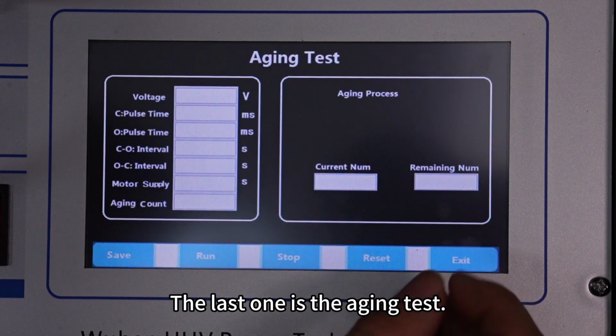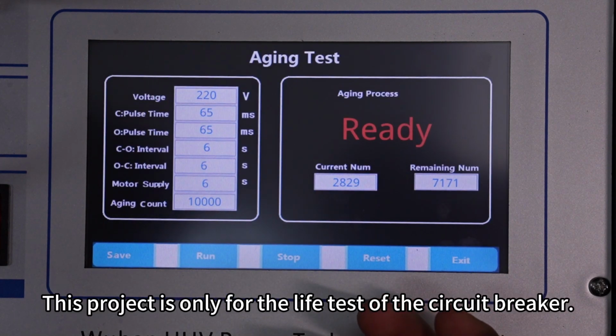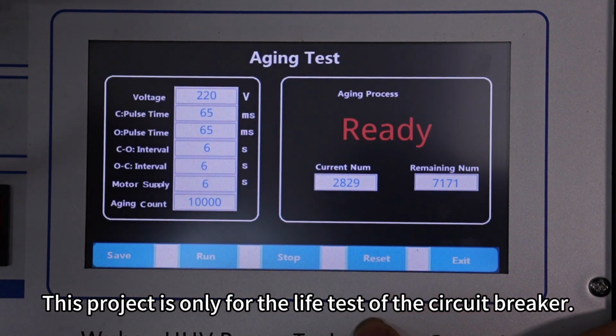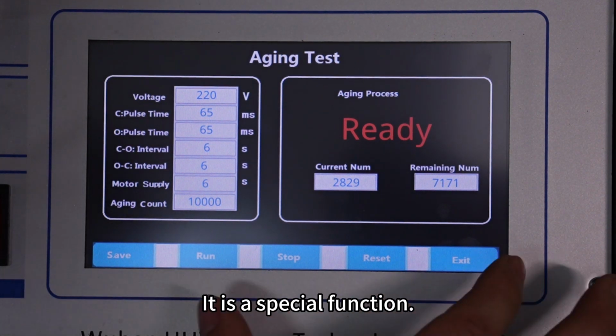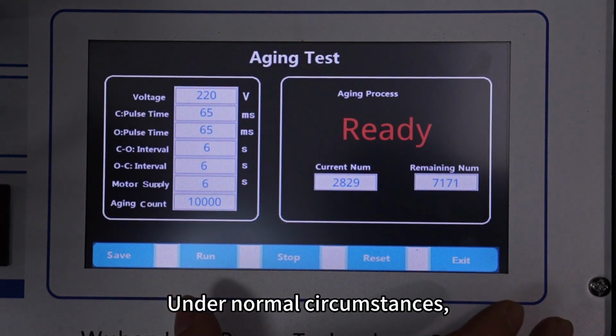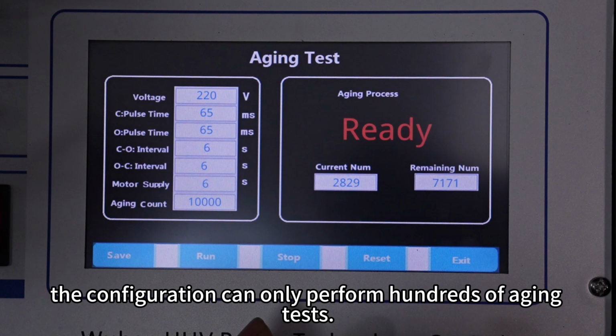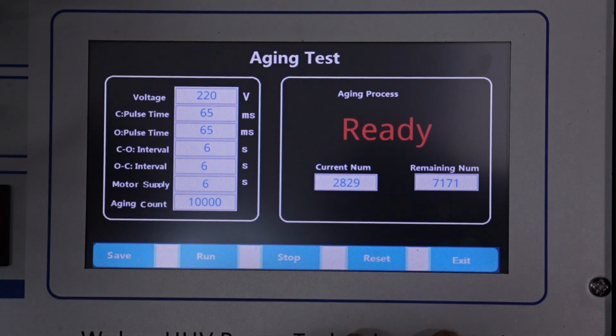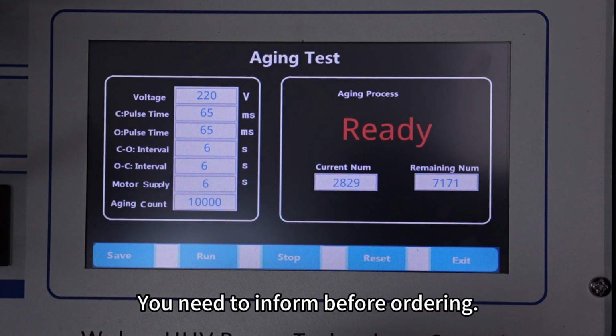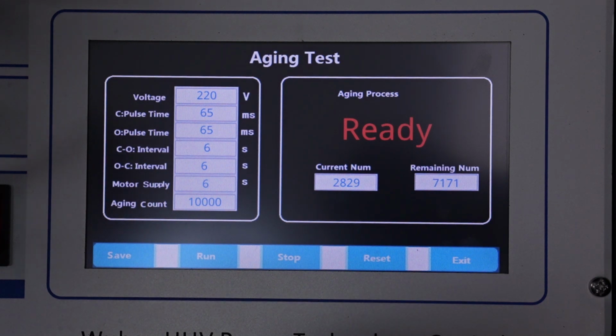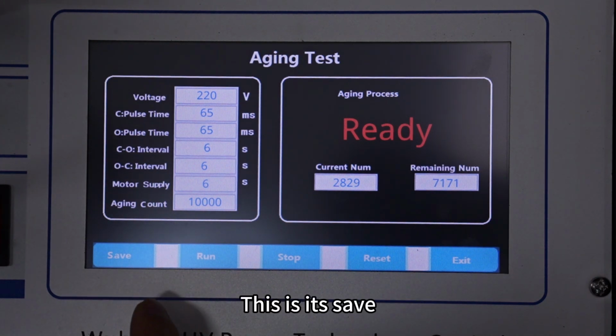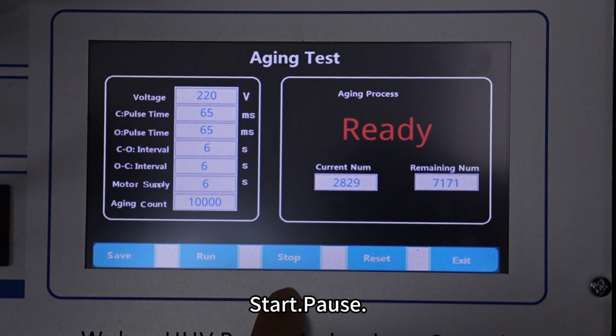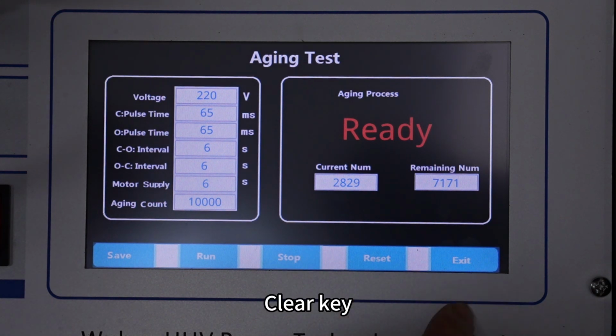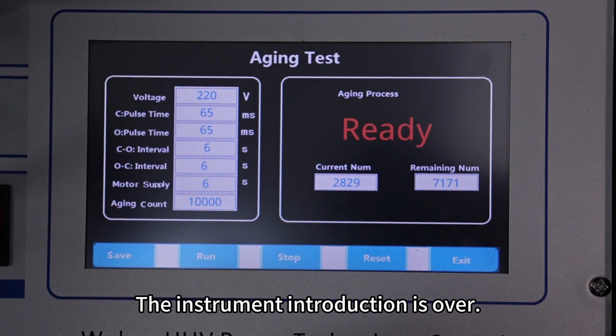The last one is the aging test. This project is only for the life test of the circuit breaker. It is a special function. Under normal circumstances, the configuration can only perform hundreds of aging tests. If you need to do more times, you need to inform us before ordering. This is its save, start, pause, clear key, exit key. The instrument introduction is over.